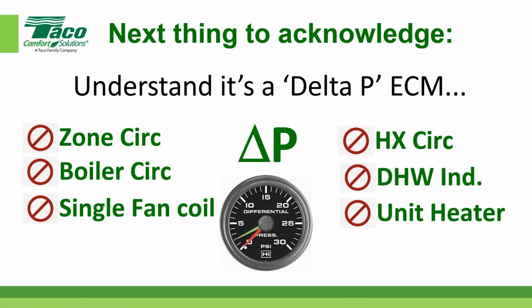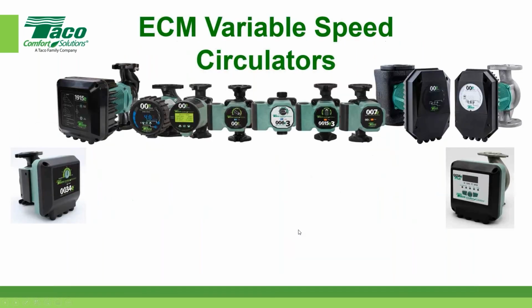And you say, well, I've done this and it's worked fine for me. Yeah, it might have worked. All that means is you never had any errors. The boiler never locked out. But you have to ask yourself the question, how much better could it have been if I had put it in the right mode and I got the circulator to turn down to the mode that was more appropriate? So anyway, hopefully that helps.